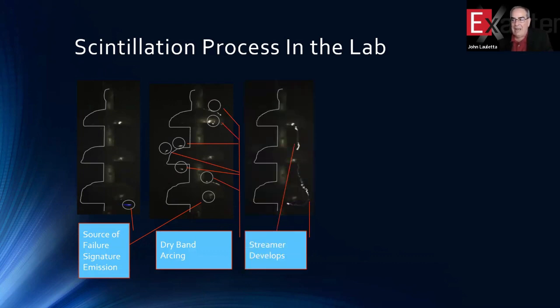And as we add these dry bands, the insulator itself begins to create streamers. These are not a flashover yet. These are arcs jumping from point to point on the insulator itself.